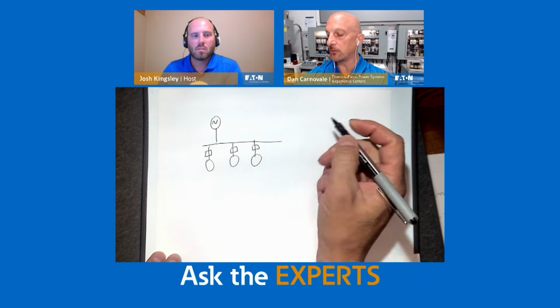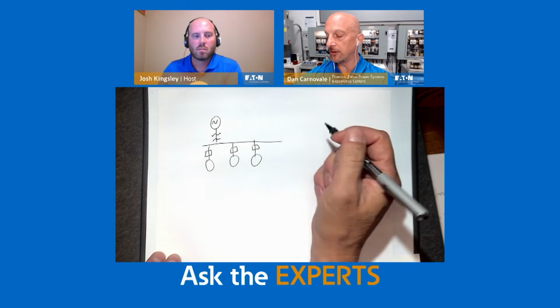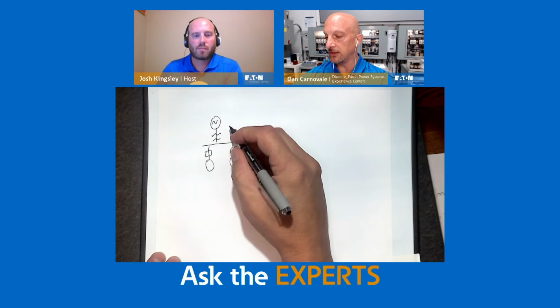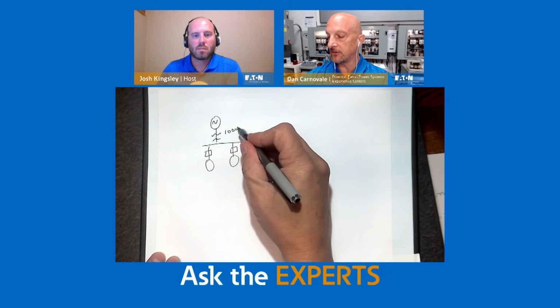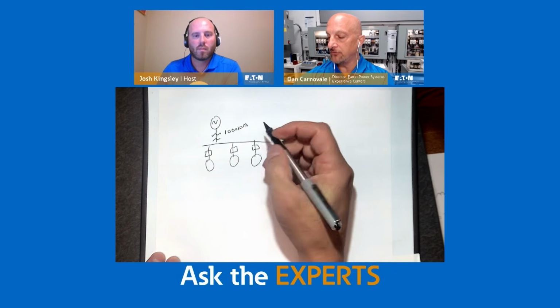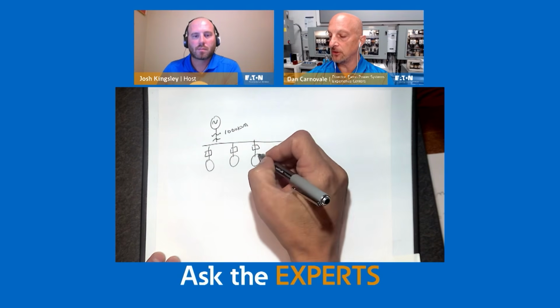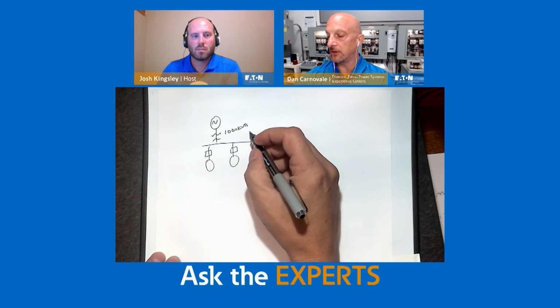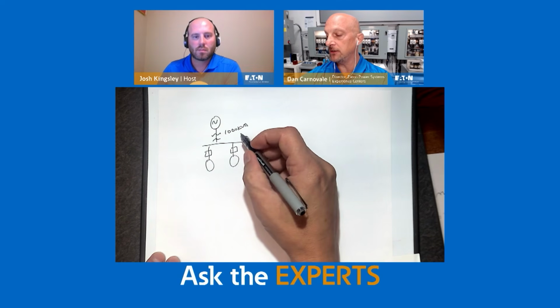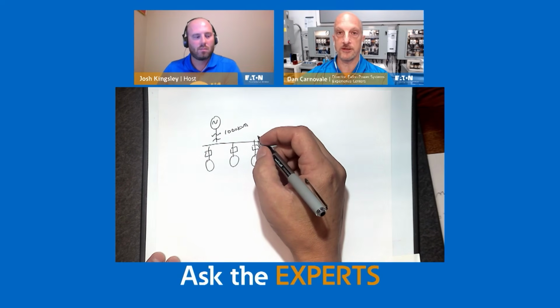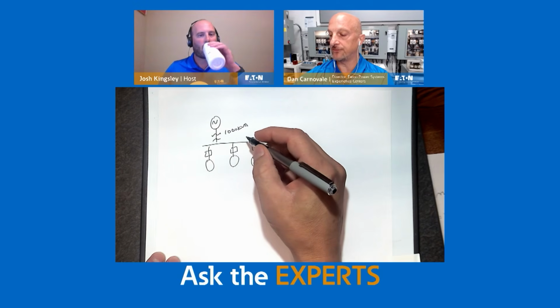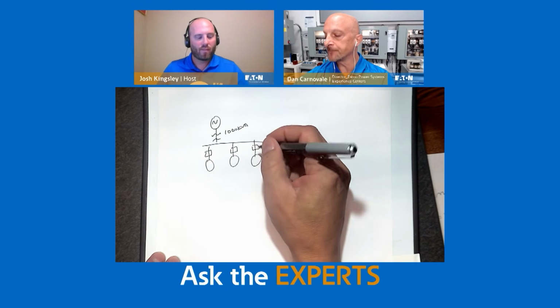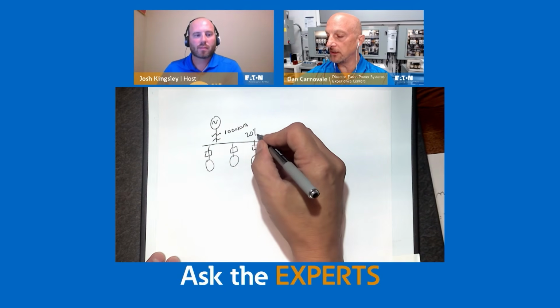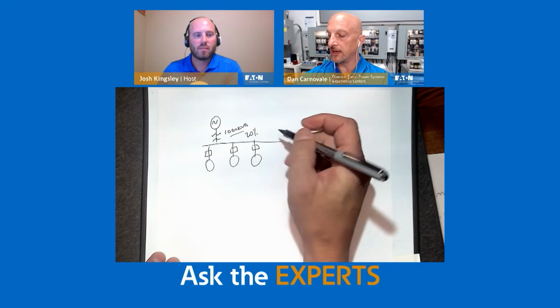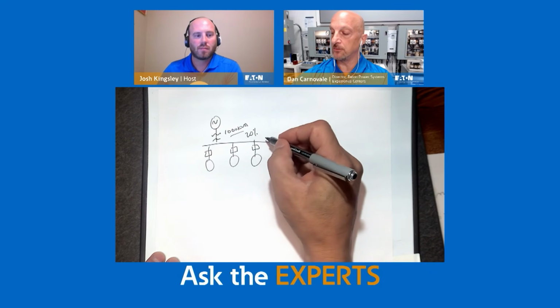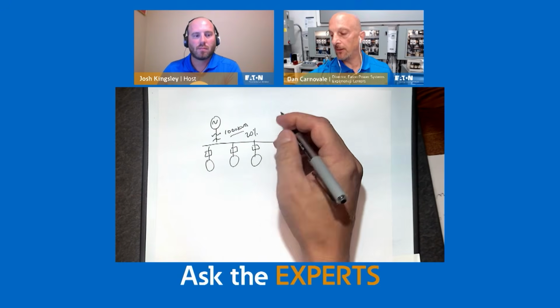At what point do you have a problem? There are some rules of thumb that we go by. If you look at the kVA of this transformer, let's say 1000 kVA, and you get to the point where about 20% of your load on that transformer is harmonic type load, then maybe you start to do some more formal analysis instead of just the back of the envelope kind of thing. So, 20% of the full load of that, which is going to relate to both the voltage and current issues.